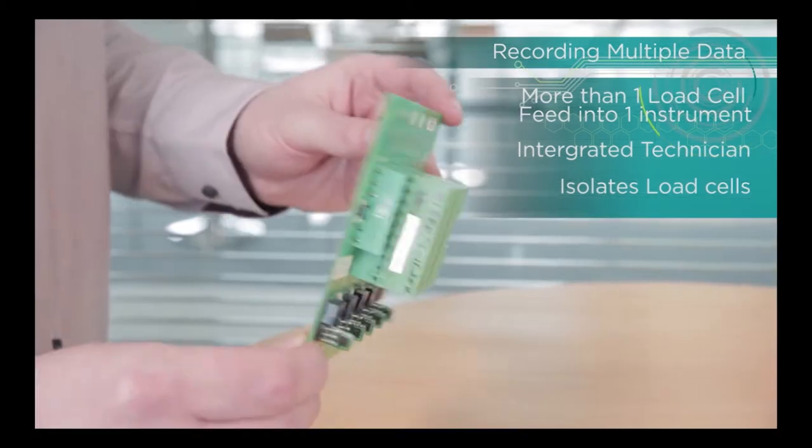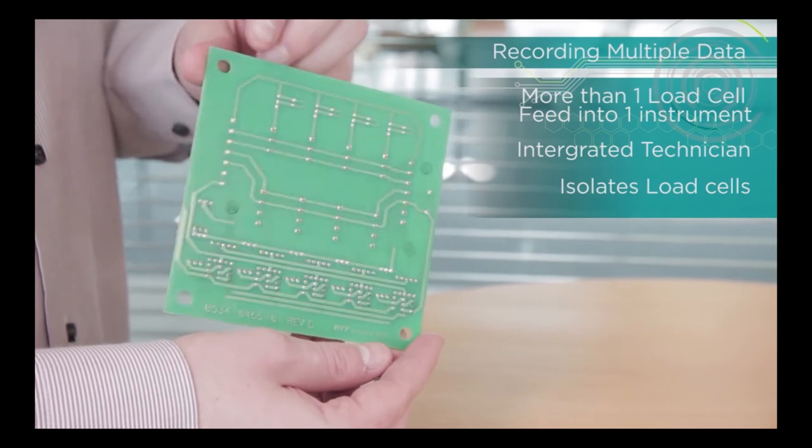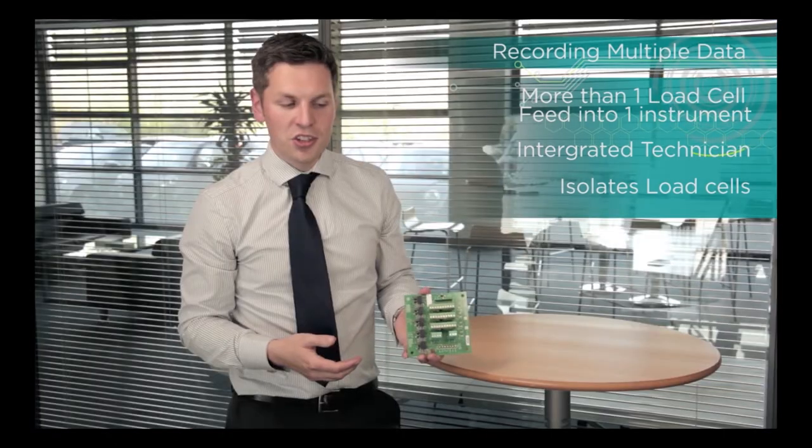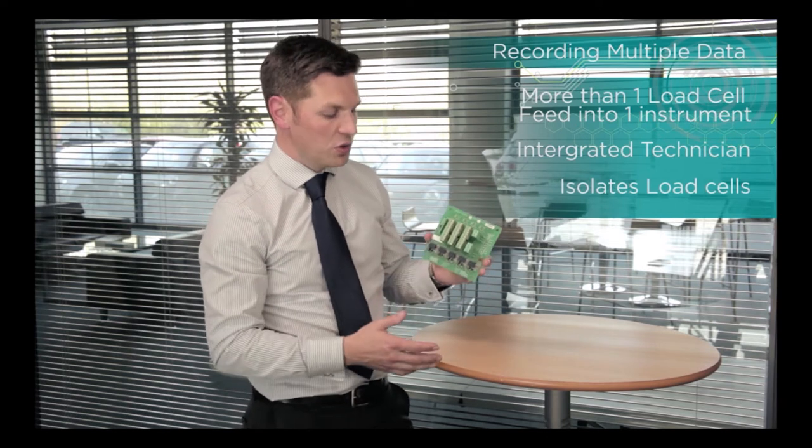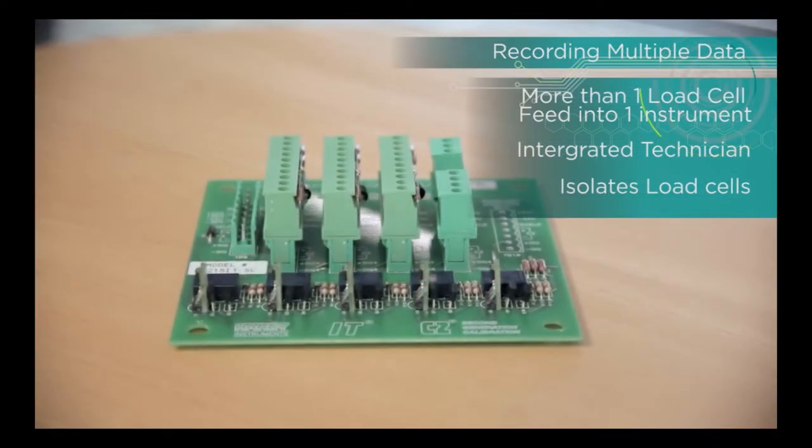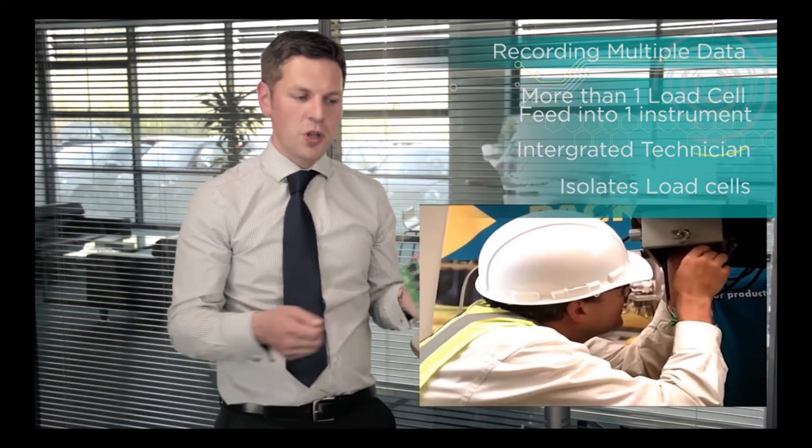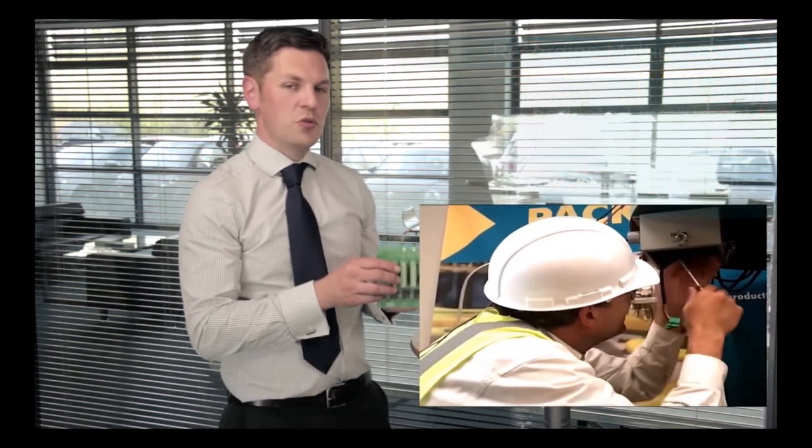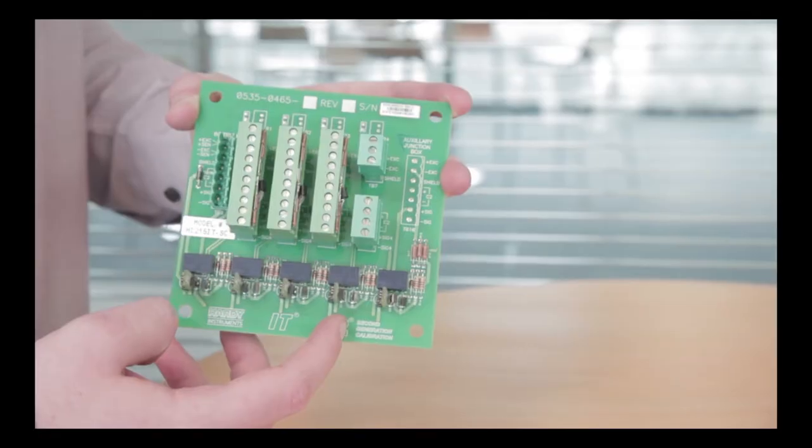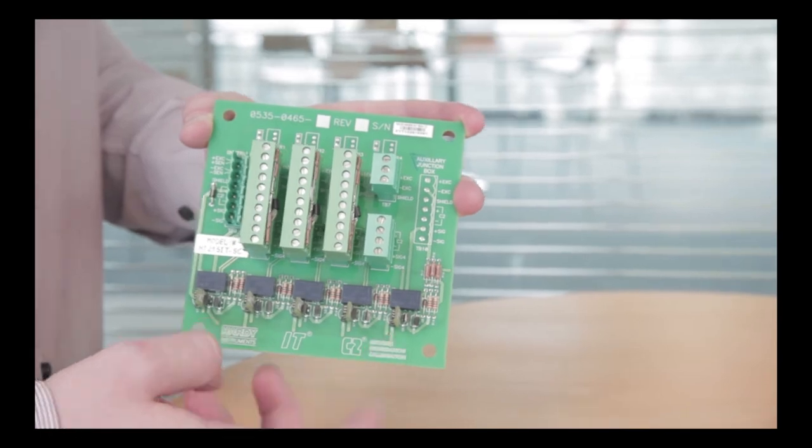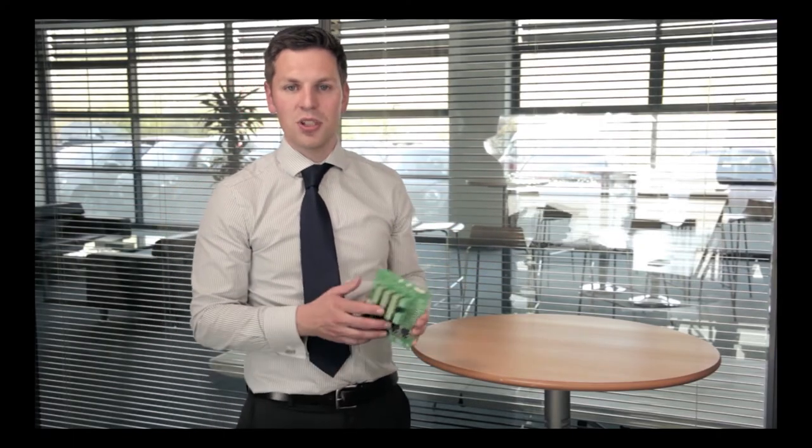But Hardy being Hardy, there's some extra features you can do. There's something called Integrated Technician which is available across most of the instruments when used with this card. Rather than going to individual load cells with your multimeter and working out which one's faulty, you can do that all from your instrument by isolating individual load cells and looking at the values coming back. There's relays on here that do that for you and you can actually do it through Internet Explorer if you're using these modules as well.